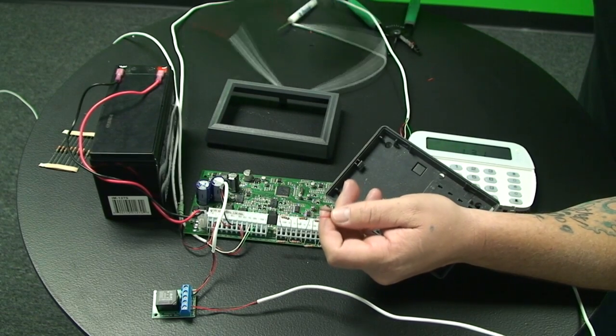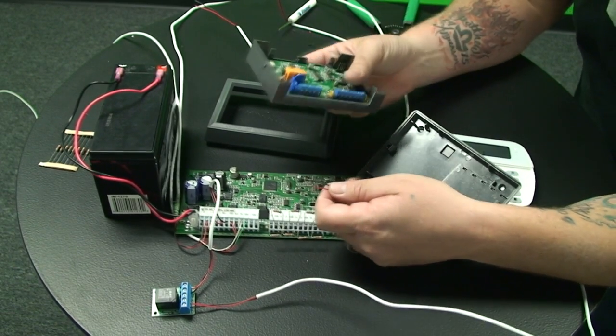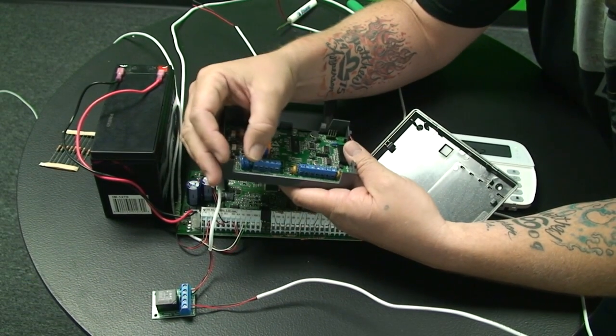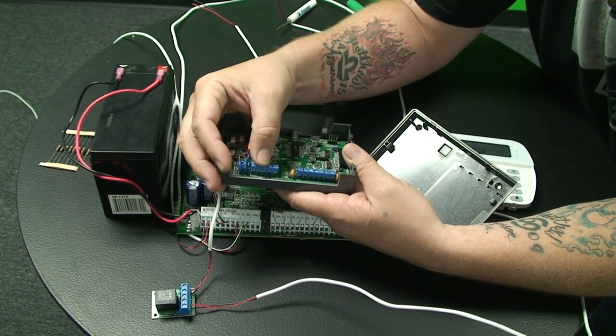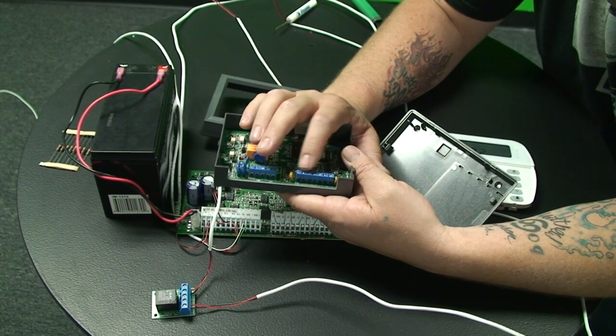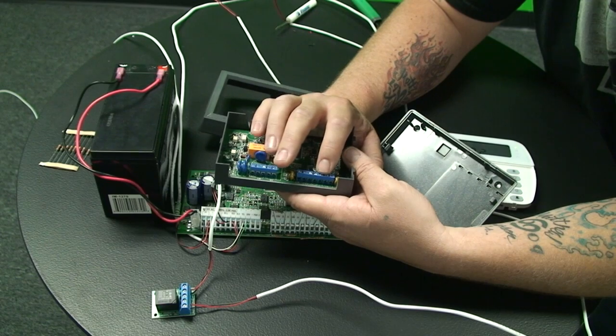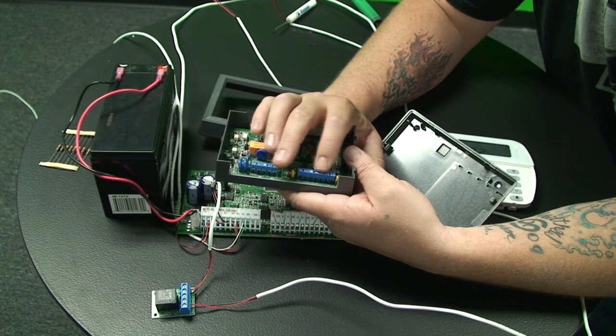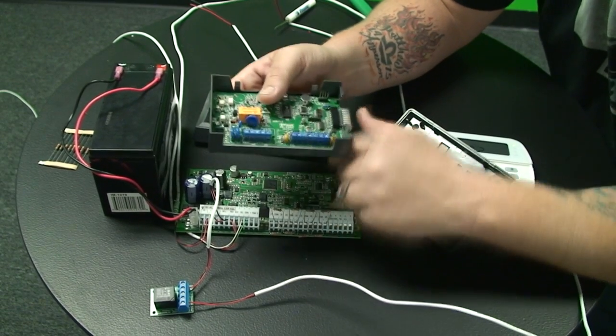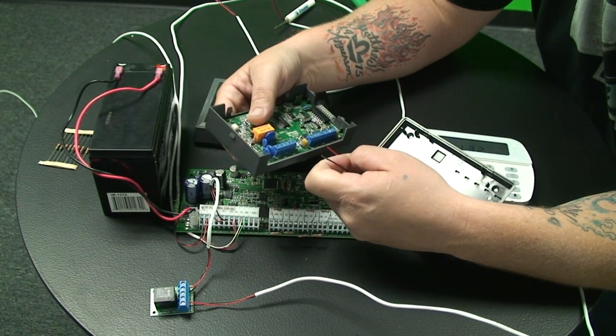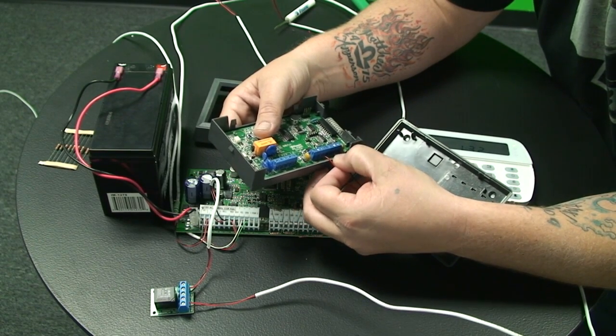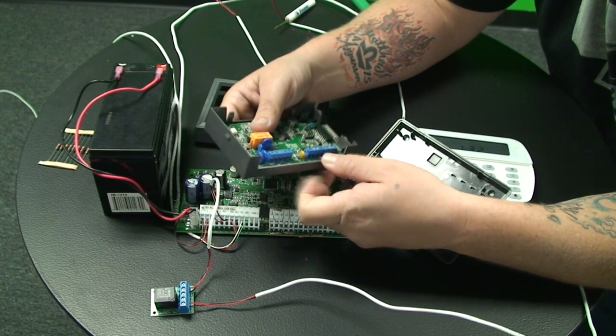And being that this came from the relay, we're going to go ahead and hook this up on the dialer. It's got a series of terminals here. You've got earth which is the ground, you have line, you have set, and then you have your positive and your negative voltage. And then there's some other terminals here which is Z1, Z2, and then the negative. Now this is where the relay is going to get hooked up here. We're going to use the Z1 terminal in this case because we only want to trigger the first channel. So again, it doesn't really matter which way they go as long as they're in, as there's no polarity there.